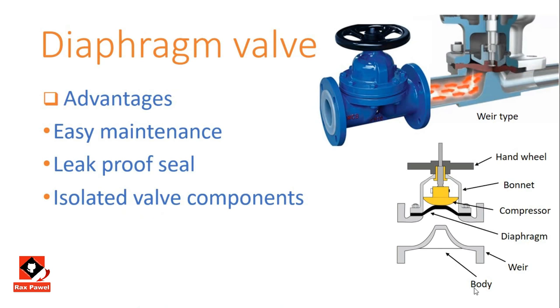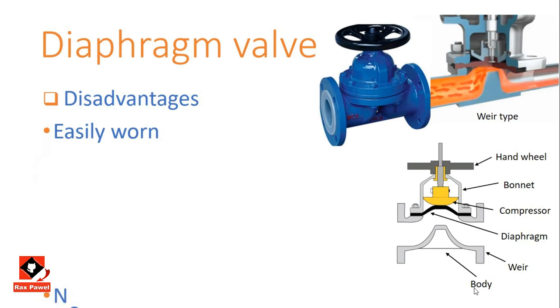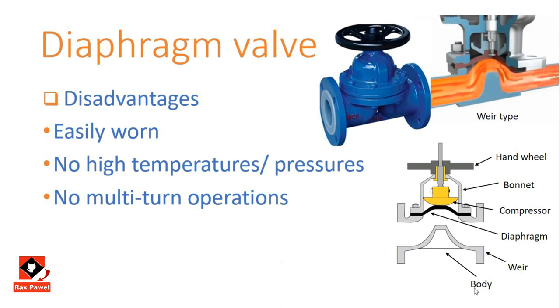Disadvantages of the diaphragm valve: the diaphragm becomes worn more easily, therefore it is not suitable for high temperature and high pressure applications. The diaphragm valve also cannot be used in multi-turn operations.